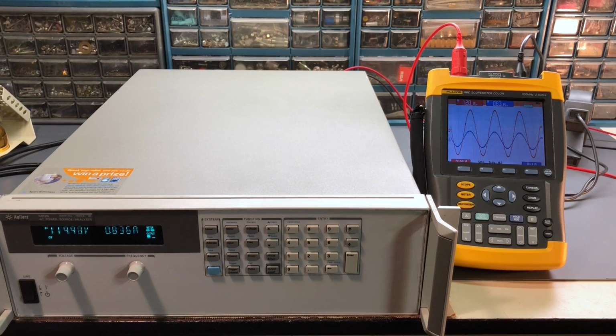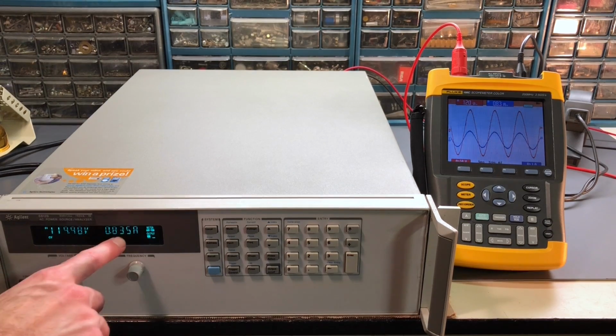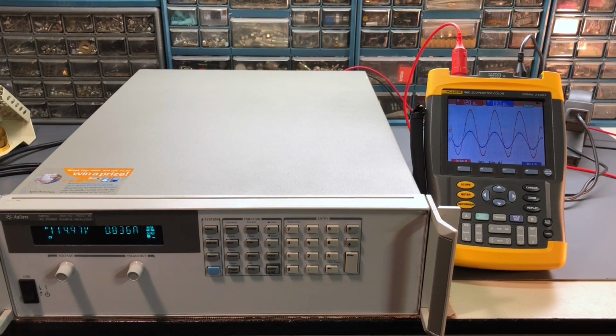Let's take a look at the constant current mode and make sure that that works all right. So you can see it says CV in the corner right here. So that's constant voltage mode, meaning it's holding the voltage constant. It's entered at 120 volts, we're right at that. And the current value will vary depending on the connected load. So typical of most power supplies where you have a regulated output voltage and then the current varies as you change the load. So we can see over on the Fluke Scopemeter, it's indicating 120 volts and then 0.83 amps. And right here we do have 0.836 amps, so that's an agreement.